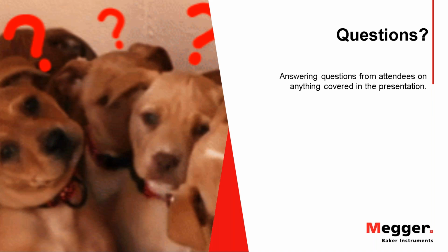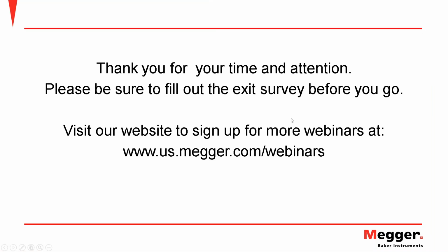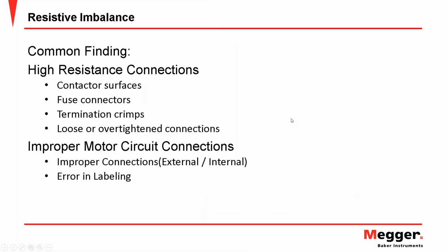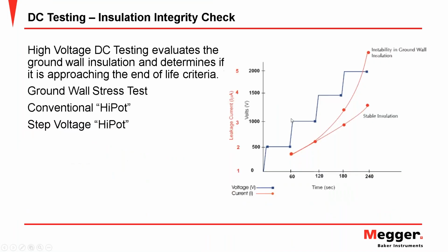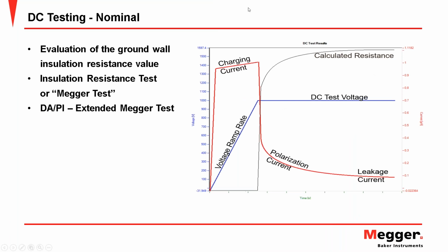Another challenge of really long cables is during DC testing, the charging current, that current at the very beginning of the, let's see if I can slide back to it really quickly. At the beginning of the DC test here, this charging current is directly related to the capacitance in the circuit. So motors with really long cables might have really high charging currents, and we'd have to reduce our ramp rates to get to test voltage in some cases. And I've been in some situations where we just couldn't test through the cables.